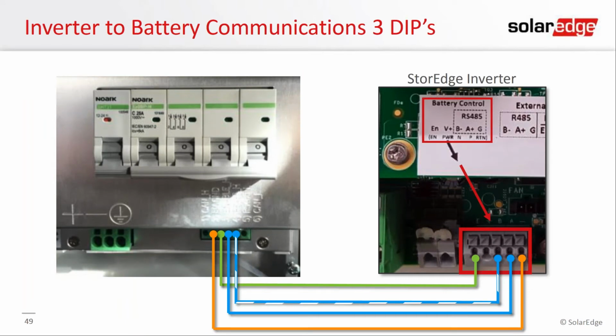The communication wires are the most tricky thing to do, but this is the format that you're going to see moving forward, where basically it's just 4 wires. So we recommend a twisted pair, a Belden or equivalent. A lot of people use Cat5. That's acceptable if you wanted to do that. I've seen people use fire alarm wire. If you wanted to use that, fine. As long as it's 22 gauge twisted pair, you're going to be fine.